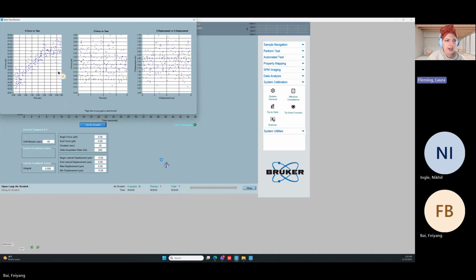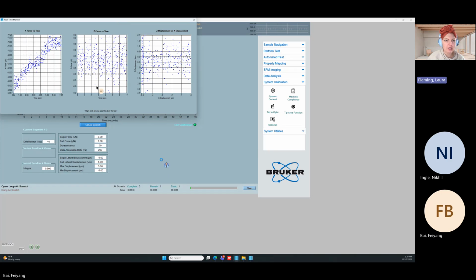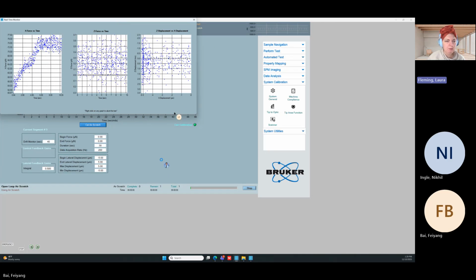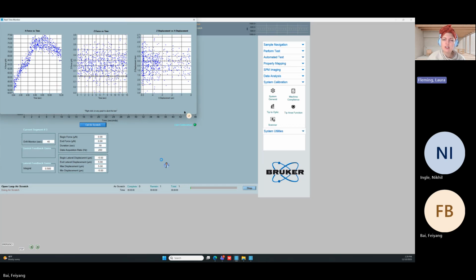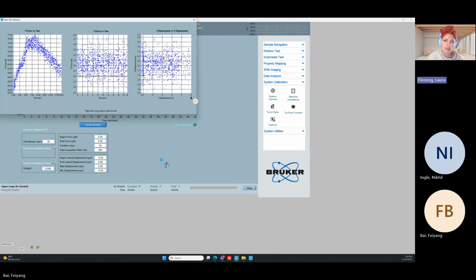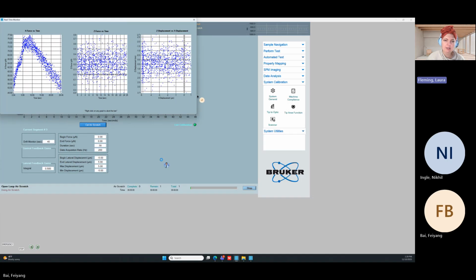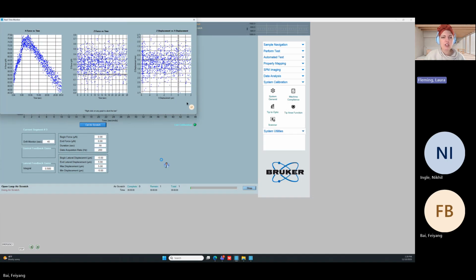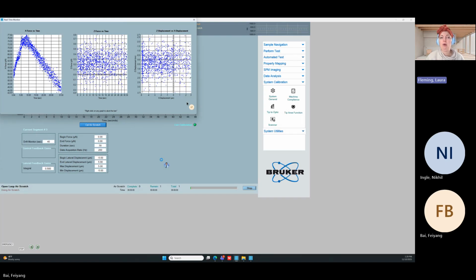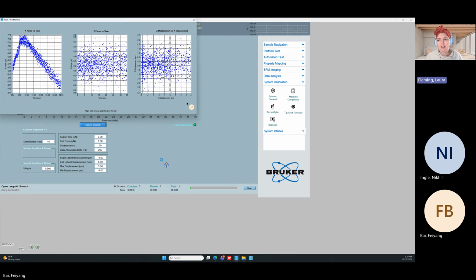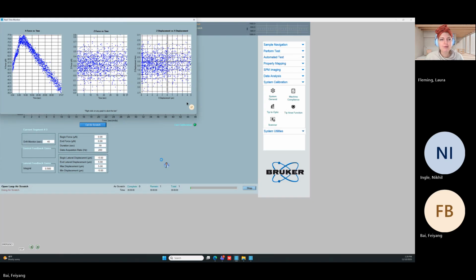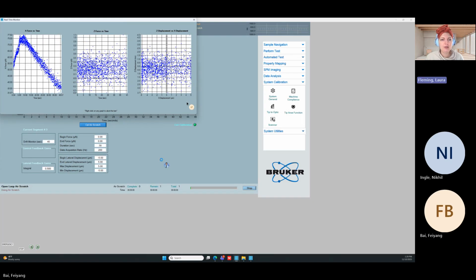Okay, so you can see here we get X force versus time, Z force versus time, and Z displacement versus X displacement. I'm typically always looking at this last graph. Is it doing what it's supposed to be doing? And it is. It's not supposed to be moving in Z. It started at 0 X and it went to negative 5 X. Now it's coming forward all the way to positive 5 before it will come back to 0. So watching the displacement lets me know that it's actuating, which is what we want to see. If it's not moving, there's something wrong and you need to call me. All right, so it went out to positive 5. And now back to 0.